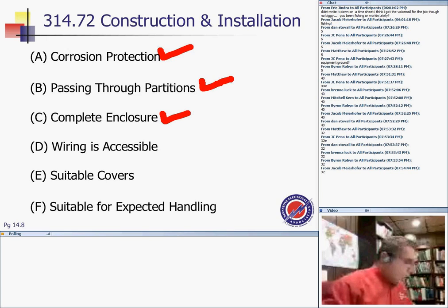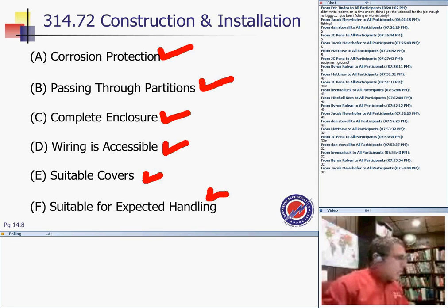So complete enclosure. Shall provide a complete enclosure for the contained conductors, no holes, nothing. Wiring is accessible. You can't go and cover the boxes after you install them. You have to cover them. Suitable covers in these underground boxes, they have to be over 100 pounds. Shall be considered meeting the requirement, and you have to say high voltage keep out. So you have to mark them with big high voltage keep out, and they are suitable for expected handling, and their cover shall be capable of withstanding the handling to which they are likely to be subjected.